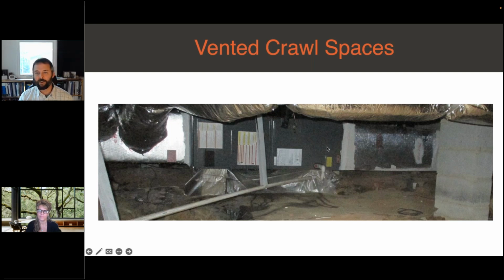So this is my plea to HVAC contractors on this webinar: think about how changing out systems impacts the space around them, because you could be taking that ambient space that was actually being cooled by duct leakage, and doing a good job with your install could actually be creating a problem. Doing the right thing could create a problem because you're not thinking overall about the impact at the end.